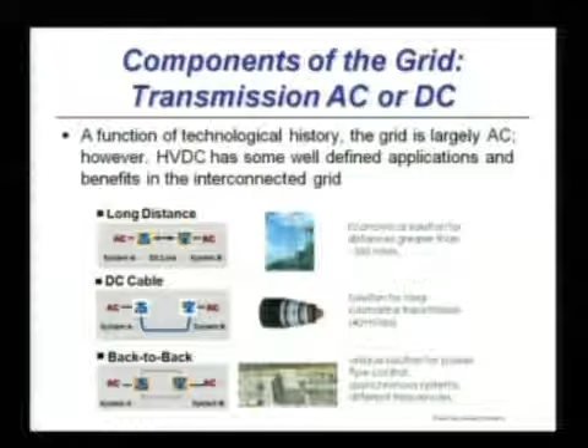The grid has evolved primarily as an AC grid as a function of technological history, but there are places and times where high voltage direct current makes a lot of sense. HVDC isn't new—it's been around since the 1950s, and in this country since the late 60s through early 70s. Once a transmission line starts exceeding about 300 to 350 miles, it starts to make sense to use HVDC for moving large amounts of power.